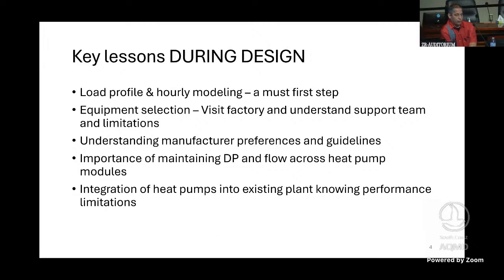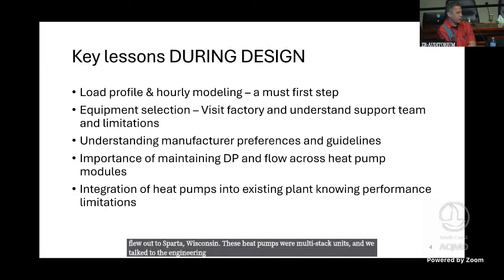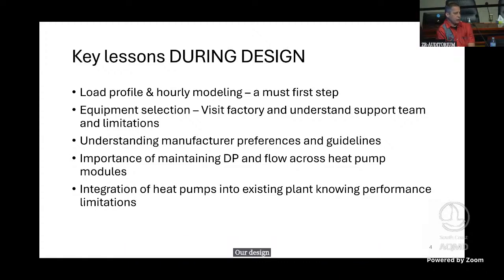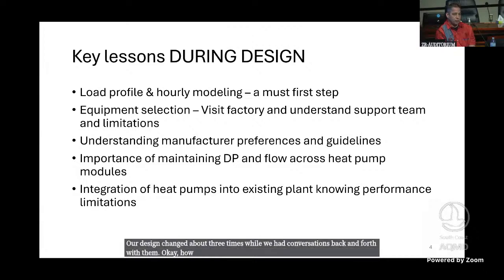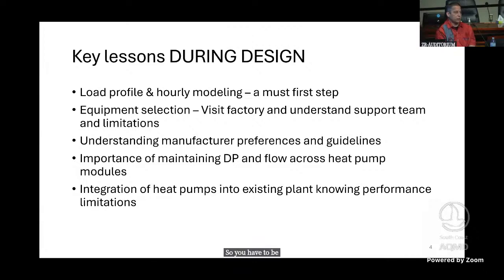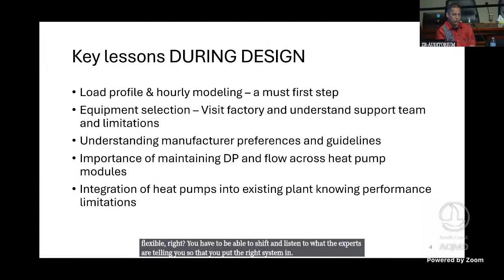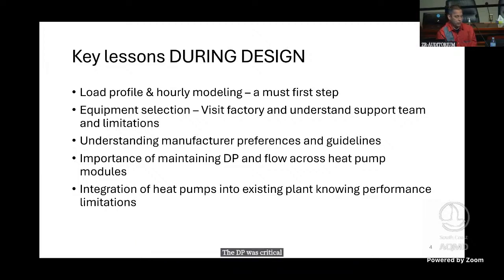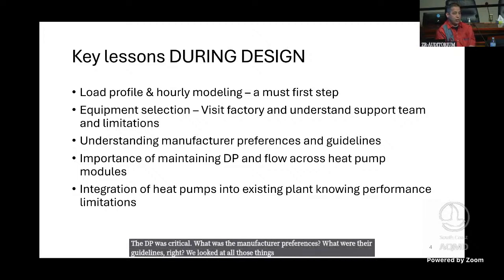We went and actually flew out to Sparta, Wisconsin. These heat pumps were multi-stack units, and we talked to the engineering team out there. We asked them, what do we need to do to design a correct system? Our design changed about 3 times while we had conversations back and forth with them. So you have to be flexible, you have to be able to shift and listen to what the experts are telling you so that you put the right system in. The DP was critical. What were the manufacturer preferences? What were their guidelines? We looked at all those things and designed a system around that.